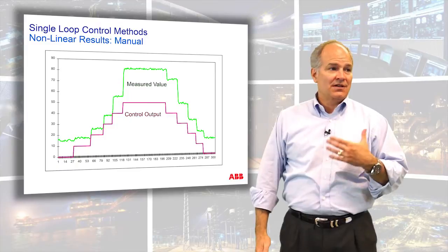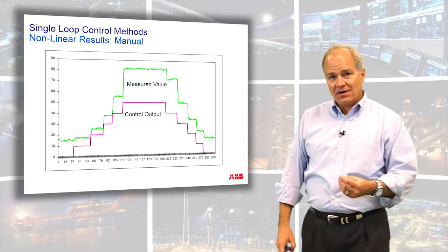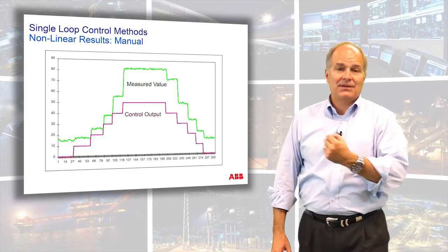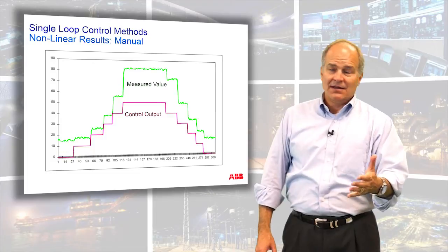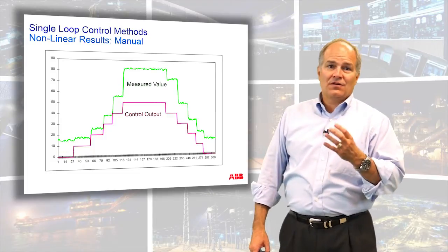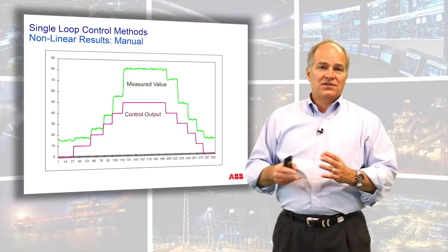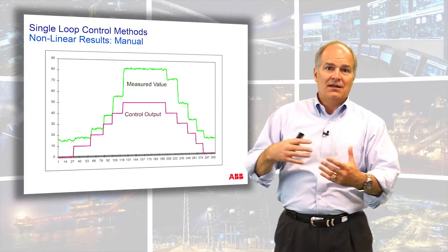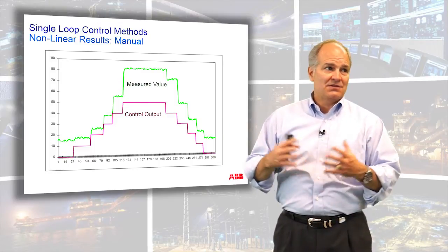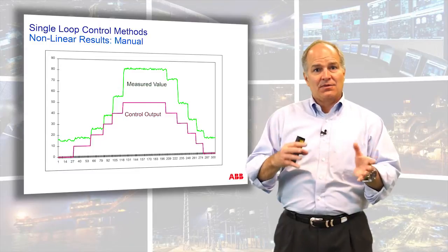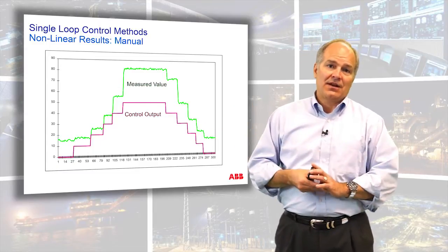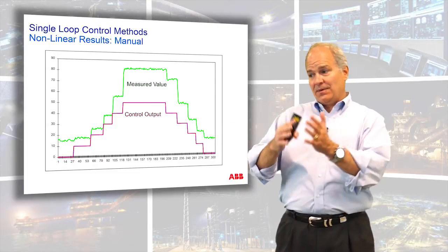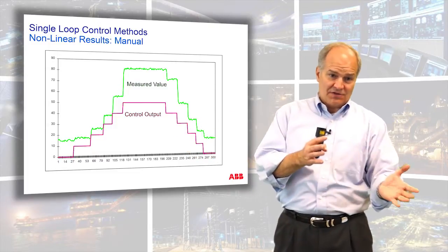When you have a nonlinear but consistent response, gain scheduling and adaptive control make sense — but don't start there. Look to see if you can come up with a single tuning number; pick the biggest process gain and it will work for all the cases. I've been to a place where on some runs the valve was at 70 percent, others at 50 percent, and when I did a bump test in both cases the gain was 10 times different. So there wasn't a number that would fit the entire operating range. We came up with adaptive control that looked at the valve position and used different tuning numbers depending on where it was, and it worked fine.